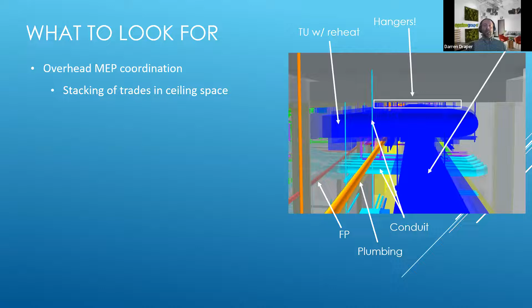So laying out those expectations, ideally with the design team early in their design, but certainly during the BIM coordination process, is important. We want to prioritize the components that require access, and that goes back to how MEP components are laid out in vertical shafts and move into the floors, impacting overall overhead access. Here are some examples from design documents showing a very busy vertical shaft for ductwork and piping, and the implications of how things come out of the shafts and stack within the plenum space overhead on each floor.